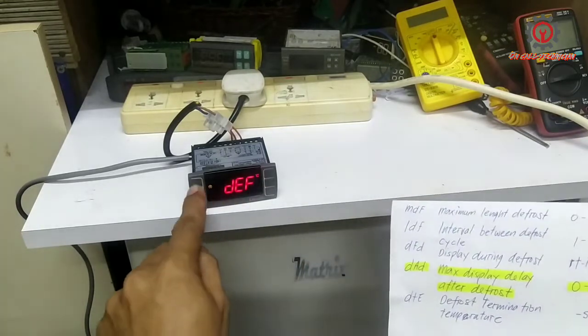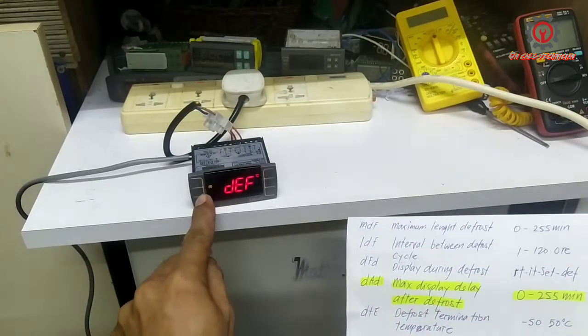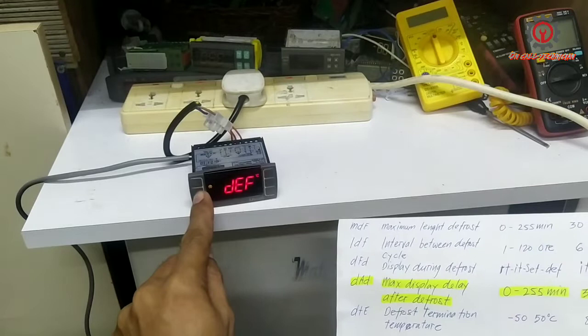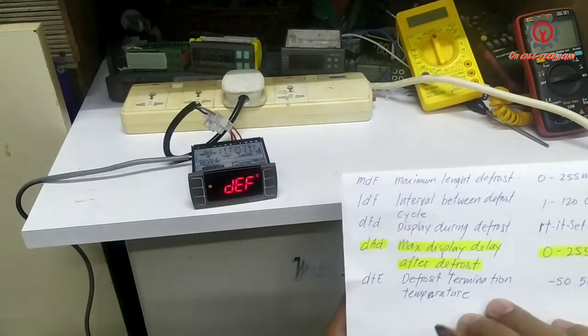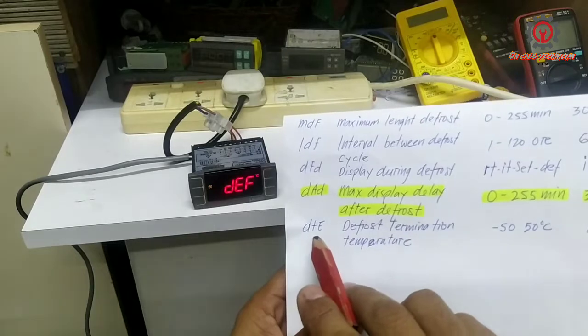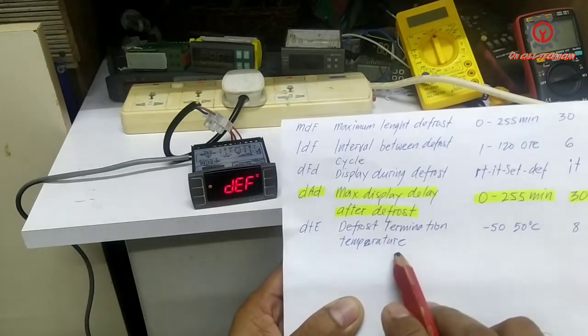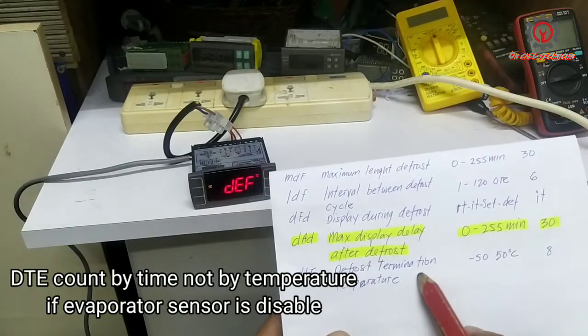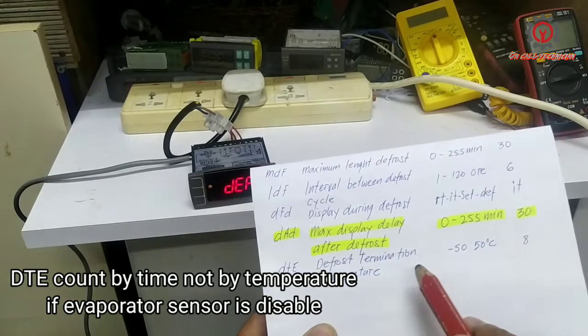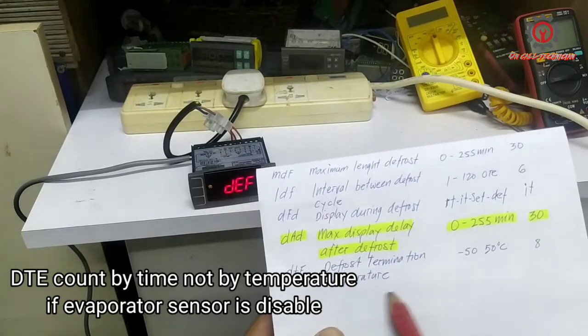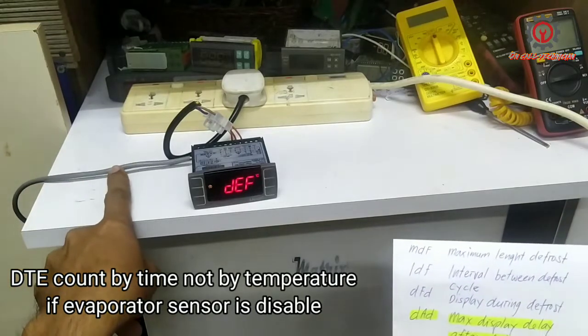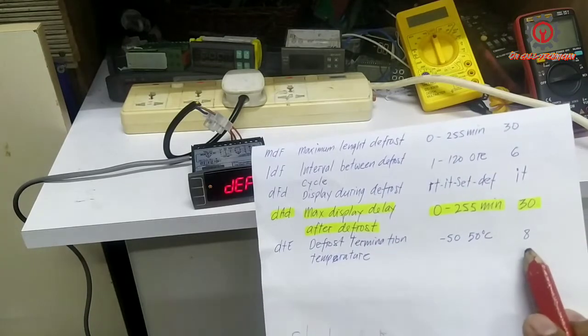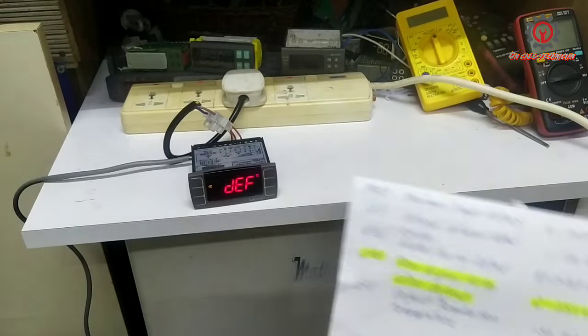We started manual defrost at negative 20. Take note our DTE, which is defrost termination temperature - if you use only one sensor, DTE is a function of time, not by temperature, because you disengage the evaporator sensor.